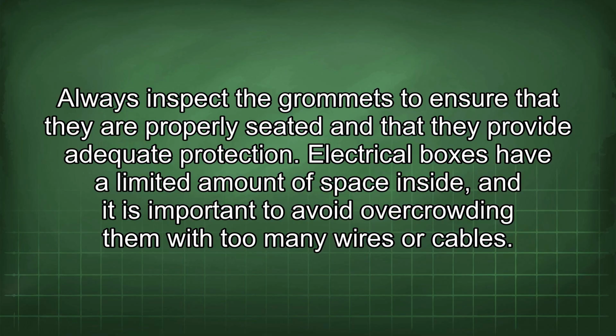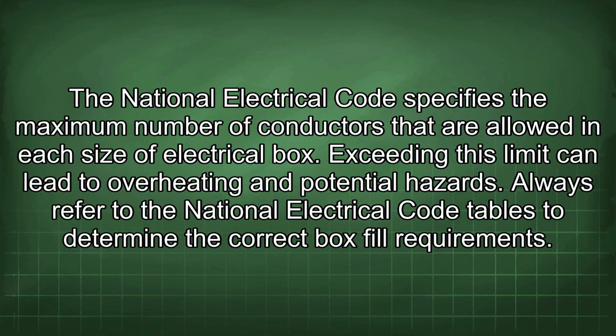Electrical boxes have a limited amount of space inside, and it is important to avoid overcrowding them with too many wires or cables. The National Electrical Code specifies the maximum number of conductors that are allowed in each size of electrical box. Exceeding this limit can lead to overheating and potential hazards. Always refer to the National Electrical Code tables to determine the correct box fill requirements.